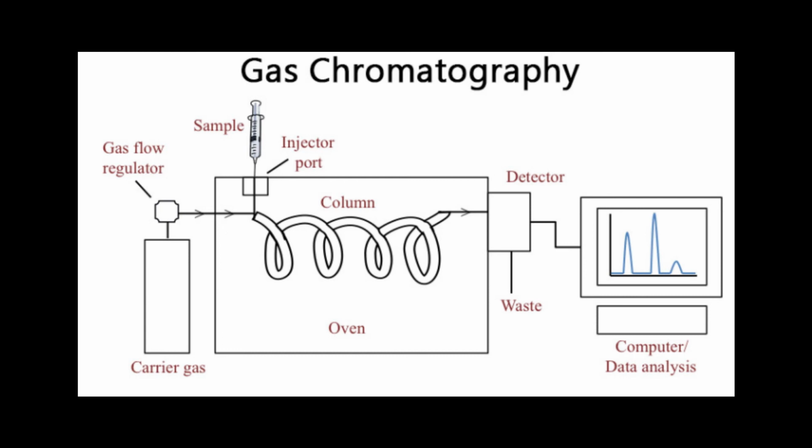That is, it is assumed that the entire sample enters the gas chromatograph at the same time, so the sample must be injected quickly. The temperature is set to be higher than the boiling points of the components of the mixture so that the components will vaporize. The vaporized components then mix with the inert gas mobile phase to be carried to the gas chromatography column to be separated.